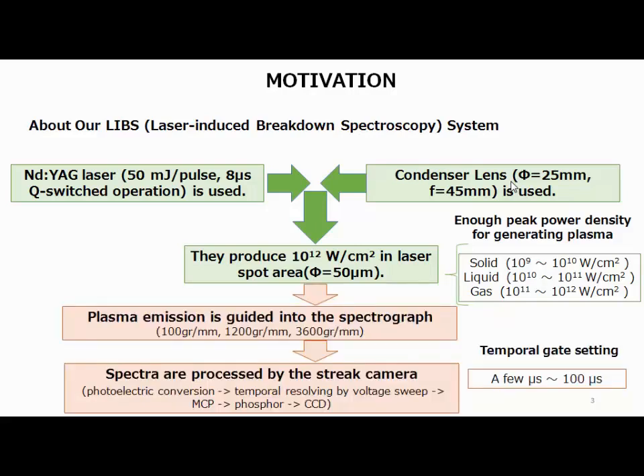The plasma emission is guided into the spectrograph. The spectrograph is a Czerny-Turner type, and the grating options are 100 and 1200 grooves per millimeter, and 3600 grooves per millimeter. The spectrograph is selectable.